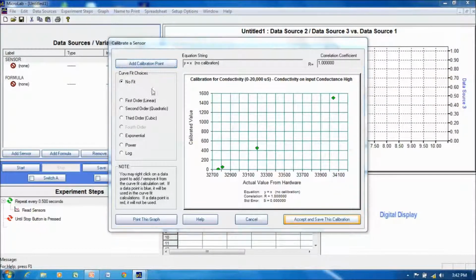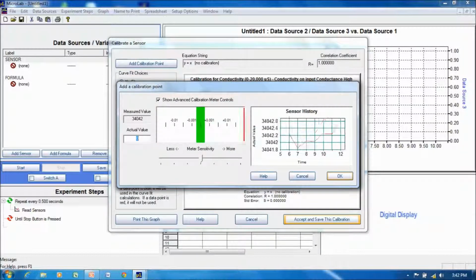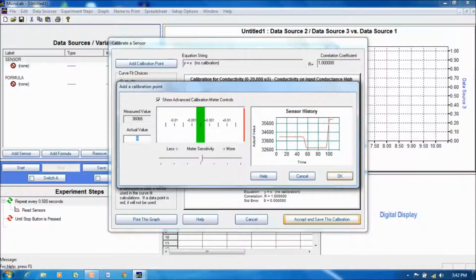Let's add one more calibration point, most concentrated solution. Again, a clean tissue, wipe down the 1500 to get that all off. Lower it into the 4500. Check for bubbles. 4,500 microsiemens per centimeter. That looks pretty good. Okay.